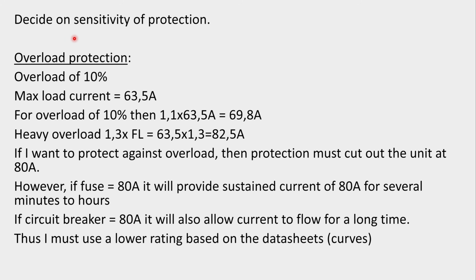When we design a protection system, we decide at what level we are going to be protecting for. In many power system applications, like your utility supplying your electricity, they would never have protection for just a 10% or 30% overload. Their protection system comes in at a much, much higher fault level because of motors and things like that. So it really depends on the application. Because this is a little electronic device, I'm kind of protecting more in the overload side rather than in the full fault level side. Right, now let's have a look at choosing the correct wire.